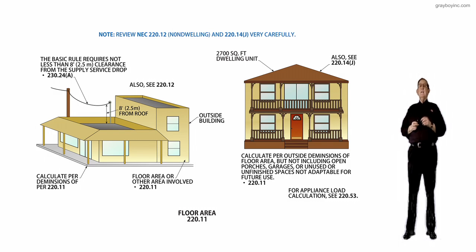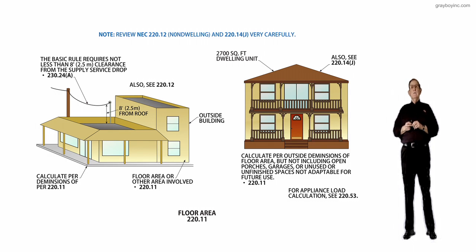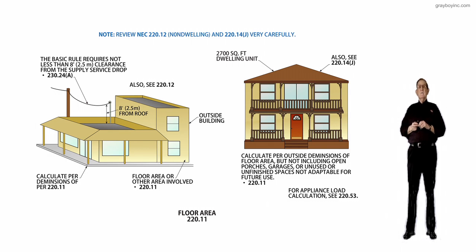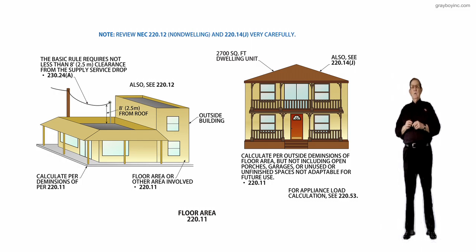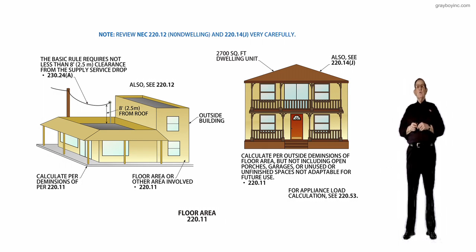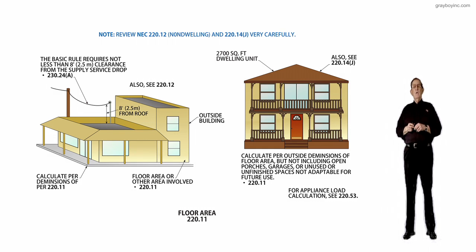The VA ratings have all changed practically, so you want to look at that table very carefully because now it's getting more in line with the Energy Code 90.1 standard. So we would get the square foot area of the facility, find out what kind of facility it is, store, office building, whatever it may be, get the VA per square foot rating, do our math, and then we would come up with the load for the service, maybe a load for feeder, depending what we were looking at.